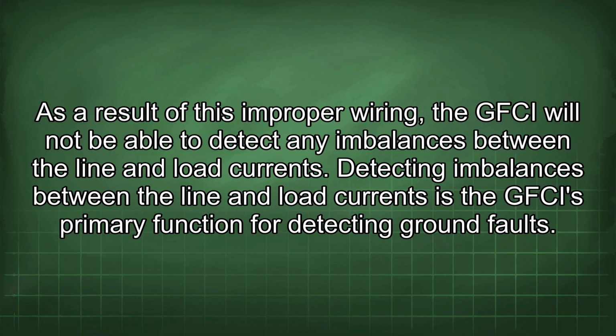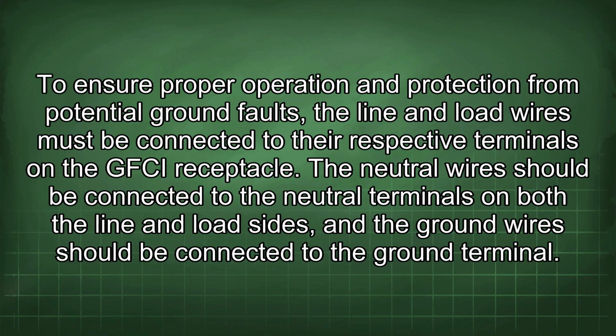As a result of this improper wiring, the GFCI will not be able to detect any imbalances between the line and load currents. Detecting imbalances between the line and load currents is the GFCI's primary function for detecting ground faults. To ensure proper operation and protection from potential ground faults, the line and load wires must be connected to their respective terminals on the GFCI receptacle. The neutral wires should be connected to the neutral terminals on both the line and load sides, and the ground wires should be connected to the ground terminal.